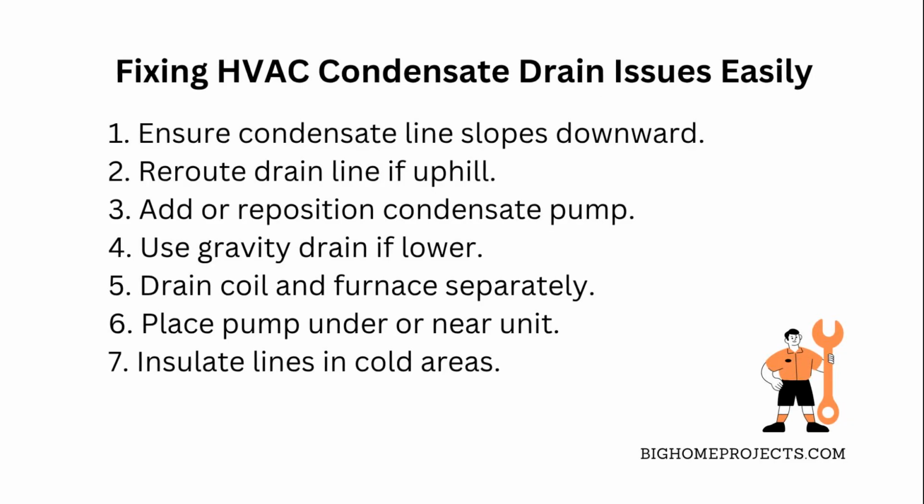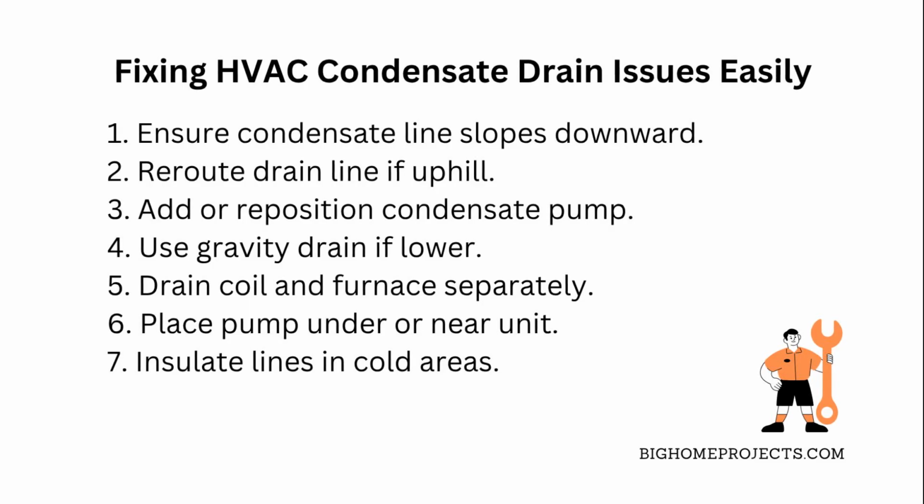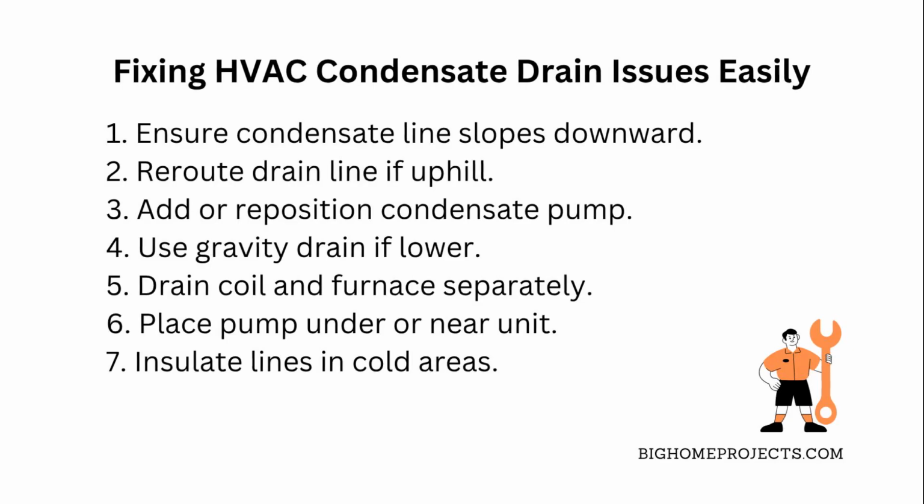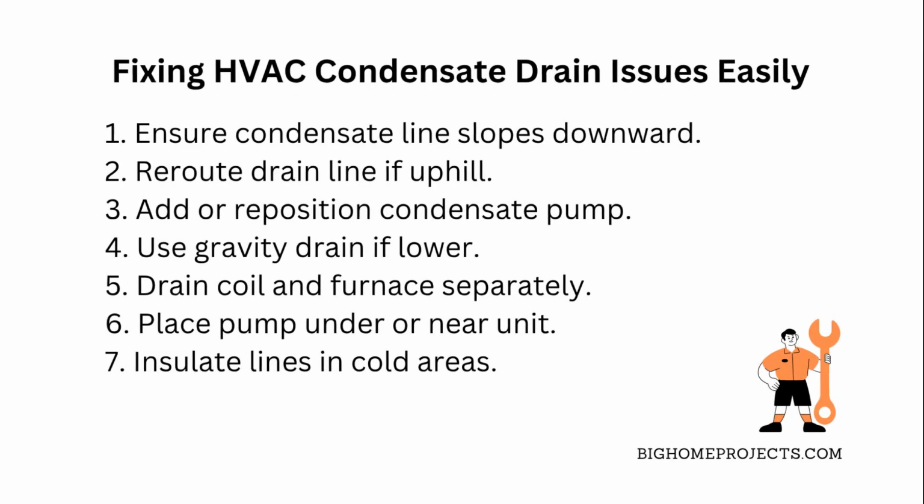About that unused drain pipe in your crawl space, yeah, you can potentially ditch the pump if gravity lets water flow directly there, but only if the drain is lower than the coil's drain pan. You gotta check the slope carefully. Water won't flow uphill or level.